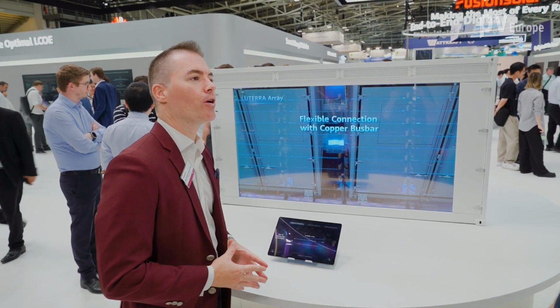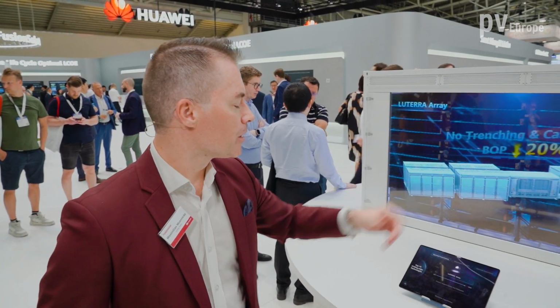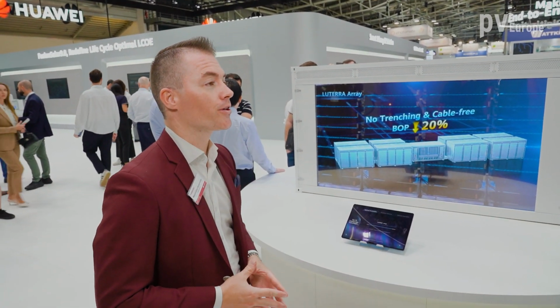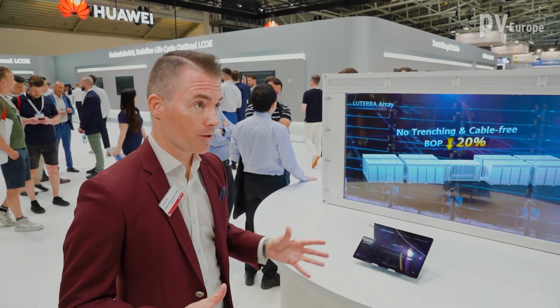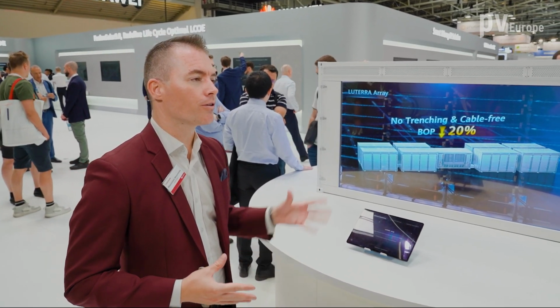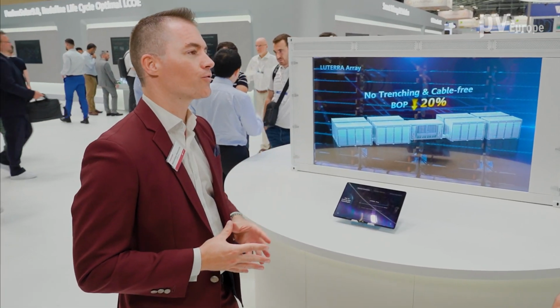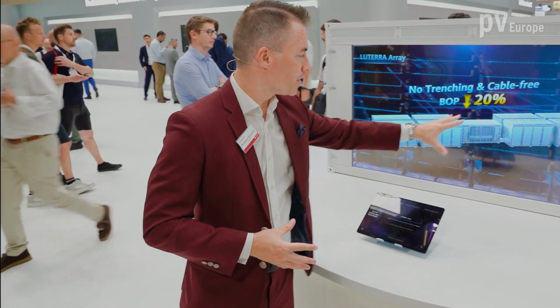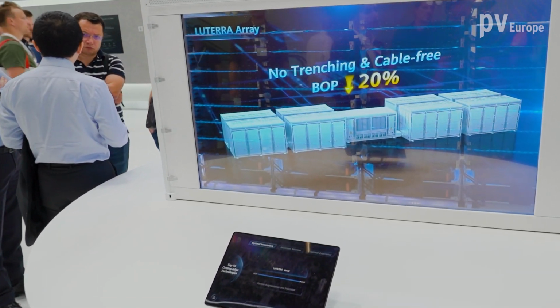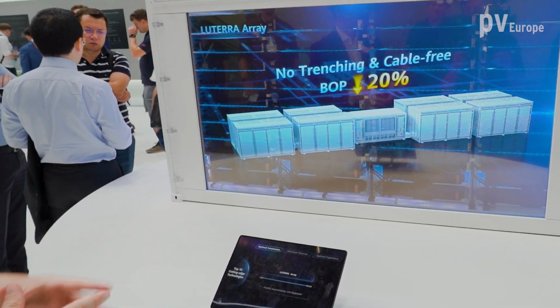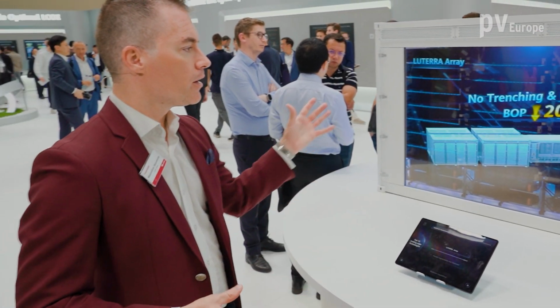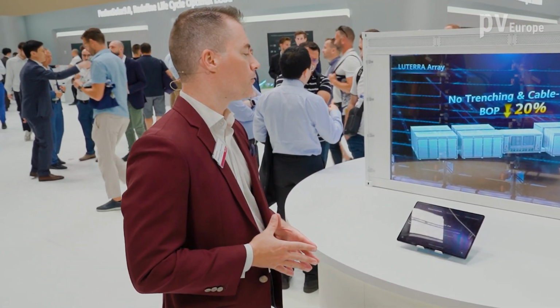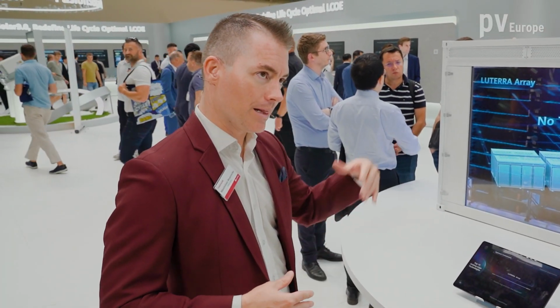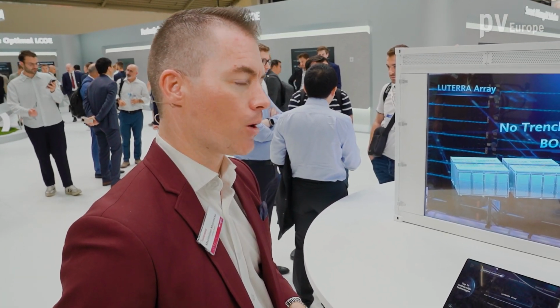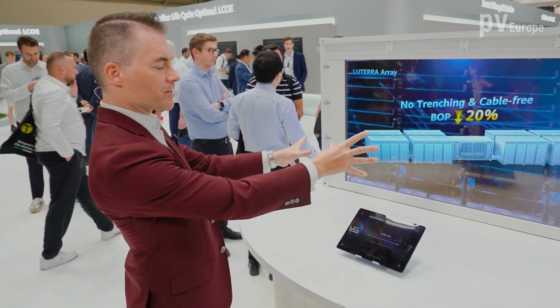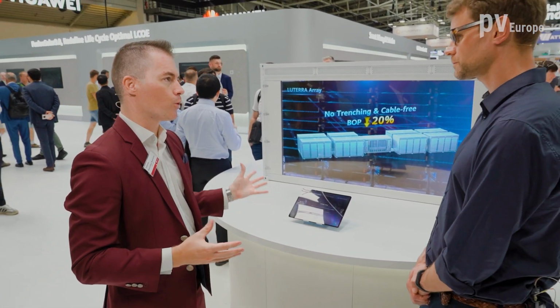First of all, you're seeing a sub-array of 9 containers. The middle one, that is our transformer station. We just talked about it in the PV section. 11 megawatt was our largest one. We have even increased that here a little bit further to 12.5 megawatt per transformer station is now the newest value. Surrounded by that is up to 8 battery storage containers. You can choose between 4 and 8. So it's a 2-hour or 4-hour battery storage system. First iteration in Q1 will be available for supply as a 5 megawatt hour battery container. Later, 6.3 megawatt hours. This means this complete sub-array with that capacity density has already 50 megawatt hours with 12.5 MVA connection capacity.